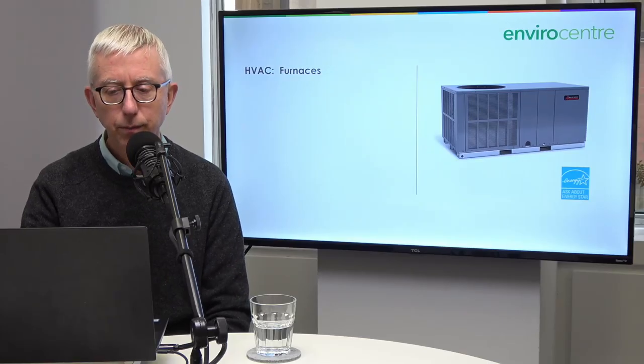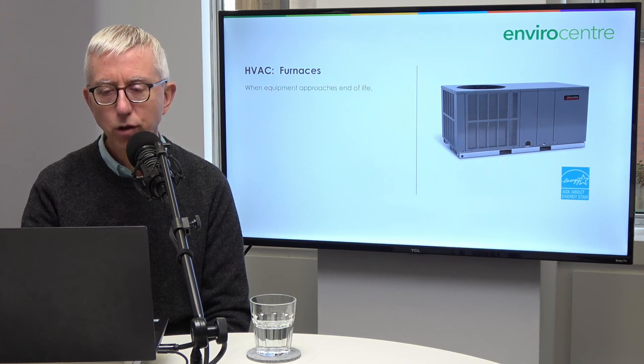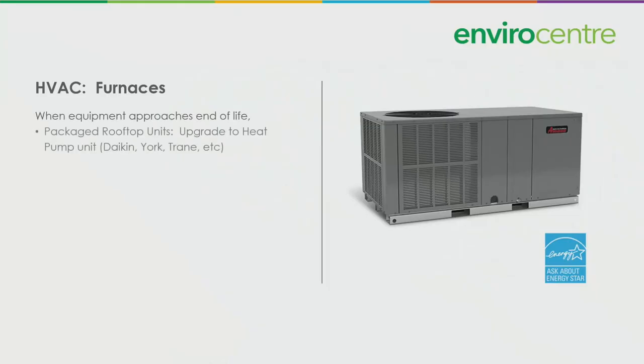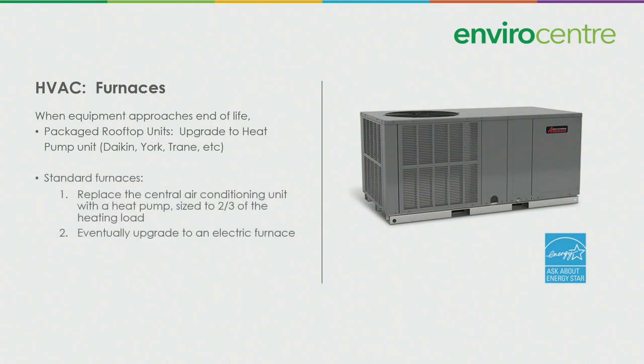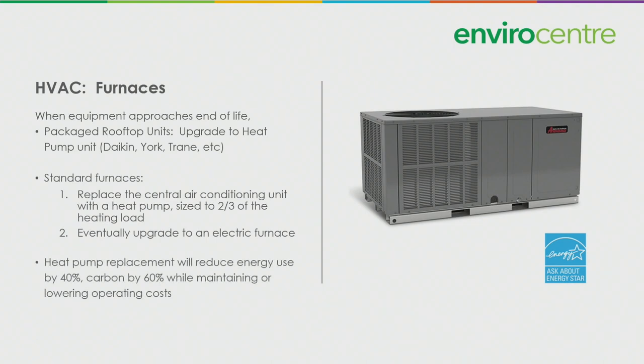For furnaces, this is a rooftop unit here. When your equipment approaches the end of life, you can upgrade to heat pumps on your roof. This is actually an Amana heat pump system that's meant as a rooftop unit. So they are available. If you have a standard furnace, you can replace your central air conditioning unit with a heat pump sized to about 2/3 of the heating load and eventually upgrade to an electric furnace.